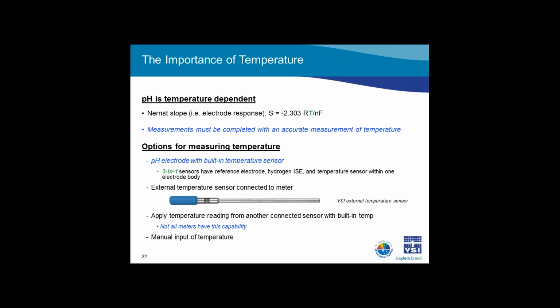Some meters allow you to use a temperature reading from a different sensor. For example, on the YSI multi-lab, if you have a different probe installed, for example, a conductivity probe that also has built-in temperature, you can use the temperature reading of the conductivity probe to temperature compensate your pH readings. Again, it is very important to understand that this is going on and to make sure that you have that second sensor in both the buffer during calibration and in the sample during measurement.